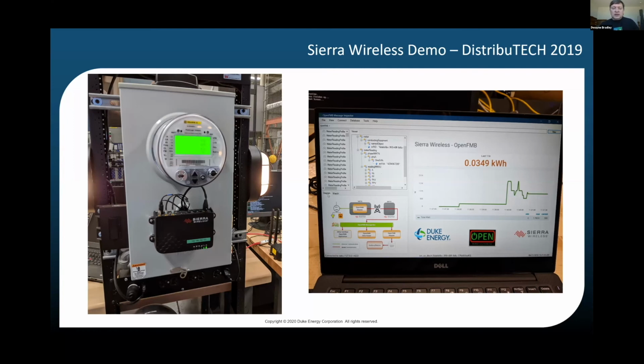So we worked with them, and they put a Docker runtime inside this Sierra Wireless device. We built one of our OpenFMB applications to talk to the meter right above it and get what that meter is seeing for power usage at any given point. We were talking to that meter every second to check the power usage. The polling is actually happening from inside this application to that meter, no outside system is polling it.